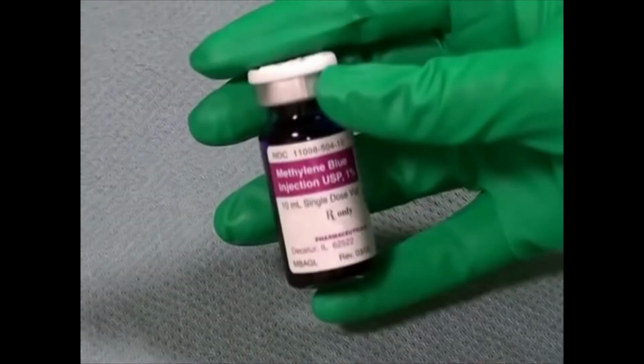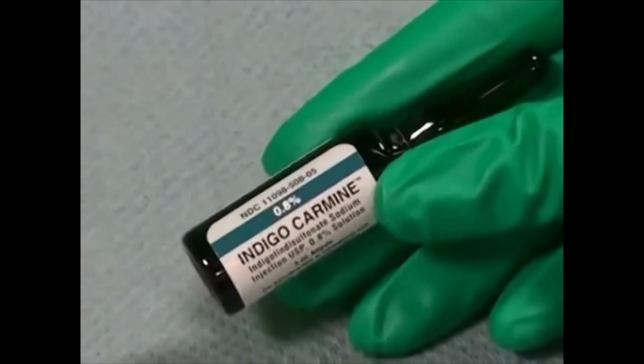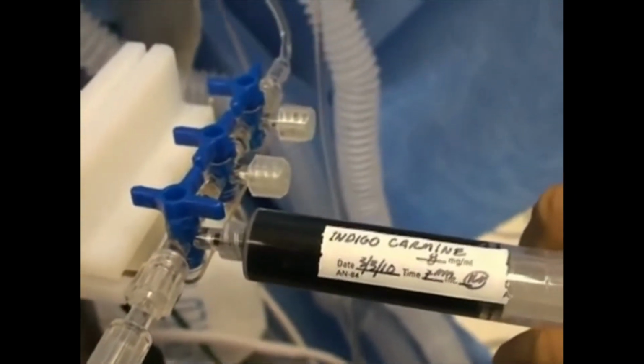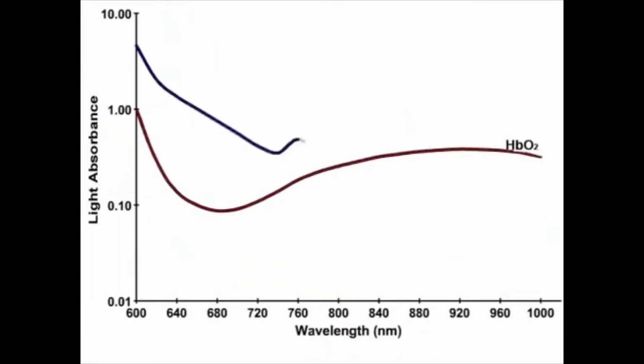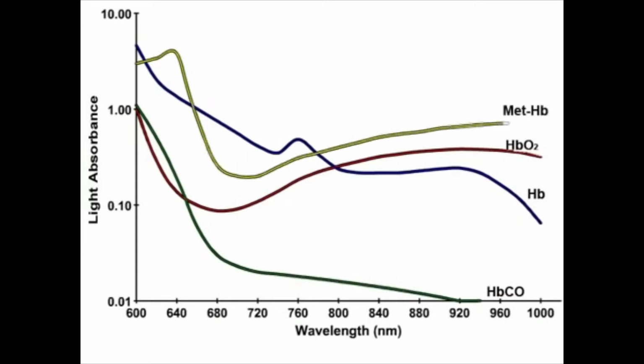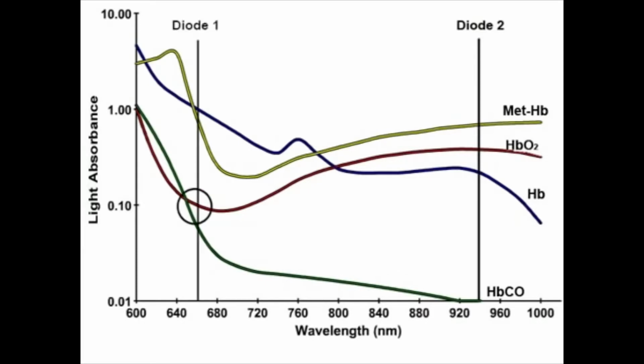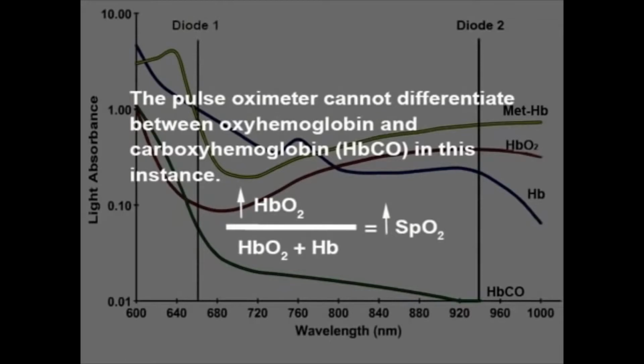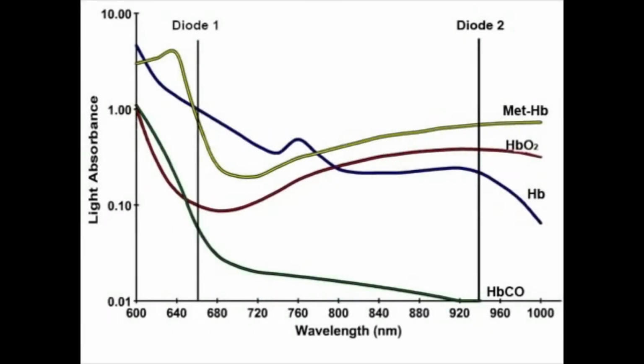The presence of intravascular dyes such as methylene blue or indigo carmine may alter the red and infrared light absorption properties of the blood and tissues, also resulting in an inaccurate reading. Non-functional hemoglobin can also result in inaccurate pulse oximeter data. At 940 nanometers, the light absorption of carboxyhemoglobin is minimal and does not affect the SpO2. However, at 660 nanometers, the light absorption of carboxyhemoglobin is similar to that of oxyhemoglobin. The pulse oximeter cannot differentiate between oxyhemoglobin and carboxyhemoglobin in this instance, and may erroneously display a normal or near normal arterial blood oxygen saturation when the actual arterial blood oxygen saturation may be low.